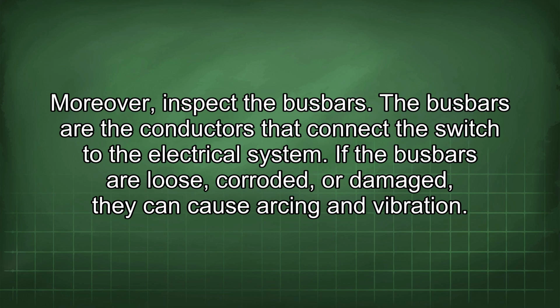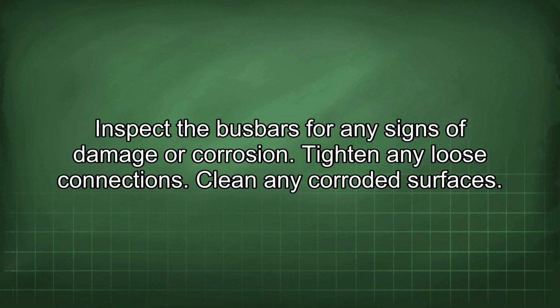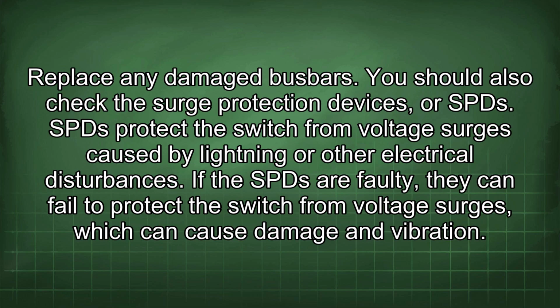Moreover, inspect the busbars. The busbars are the conductors that connect the switch to the electrical system. If the busbars are loose, corroded, or damaged, they can cause arcing and vibration. Inspect the busbars for any signs of damage or corrosion. Tighten any loose connections. Clean any corroded surfaces. Replace any damaged busbars.